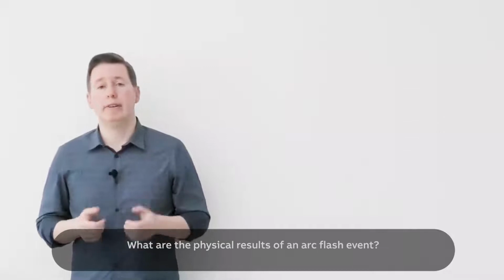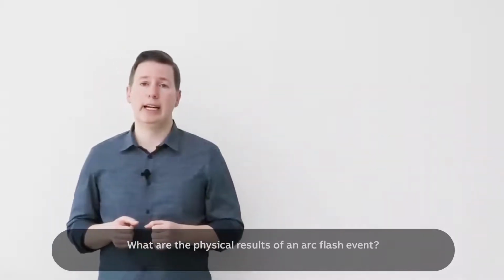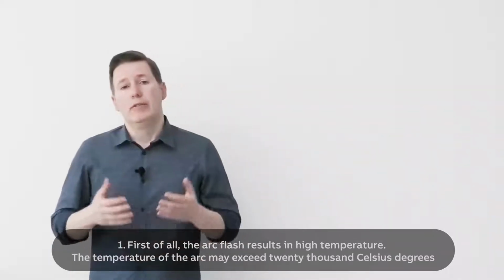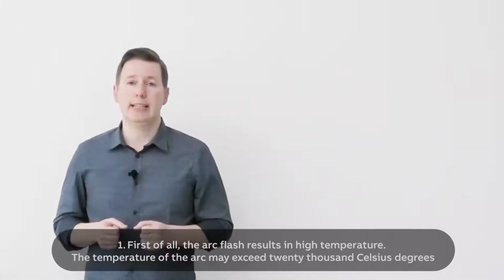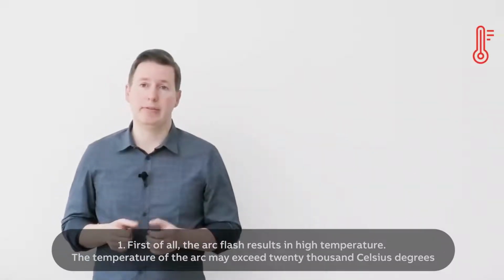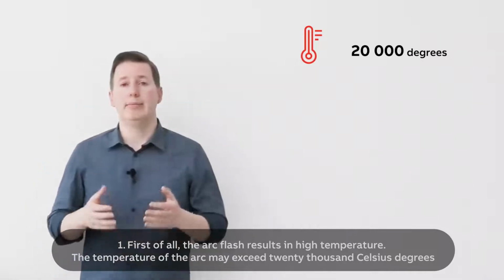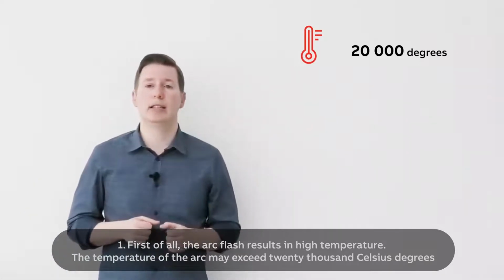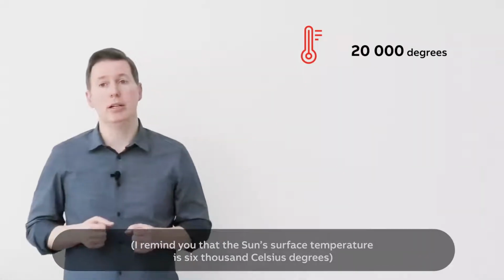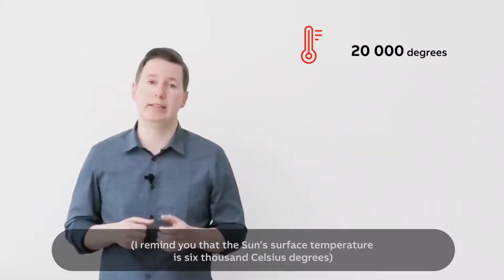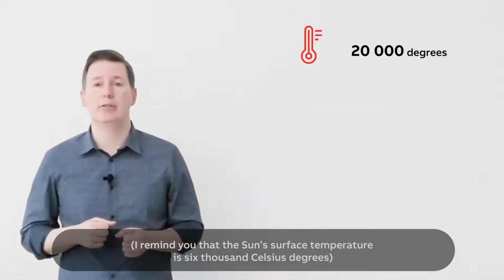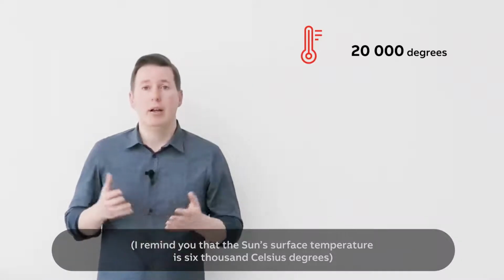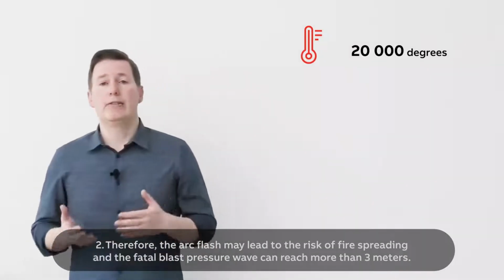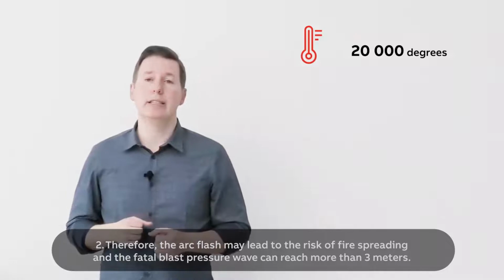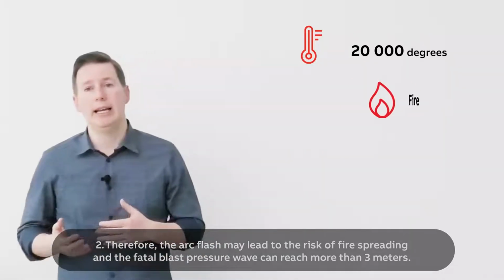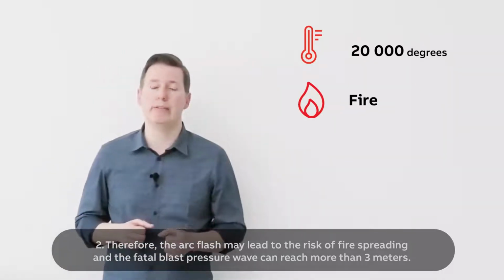What are the physical results of an arc flash event? First of all, the arc flash results in high temperature. The temperature of the arc may exceed 20,000 Celsius degrees. I remind you that the sun's surface temperature is 6,000 Celsius degrees. Therefore, the arc flash may lead to the risk of fire spreading and the fatal blast pressure wave can reach more than 3 meters.